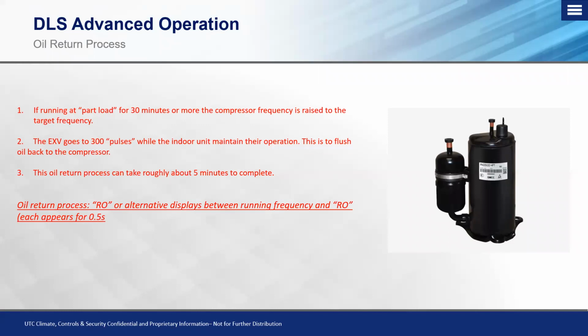One way you can confirm that an outdoor unit is in an oil recovery operation is if you look on your digital screen where we can see our running frequency, you'll see an RO on there that will alternate between the running frequency and this RO. And this essentially indicates to you that the system is in this oil return process. Once you stop seeing that alternating flash between frequency and RO, you know that the system has come out of this oil return process or oil recovery process and is back to its normal operation.